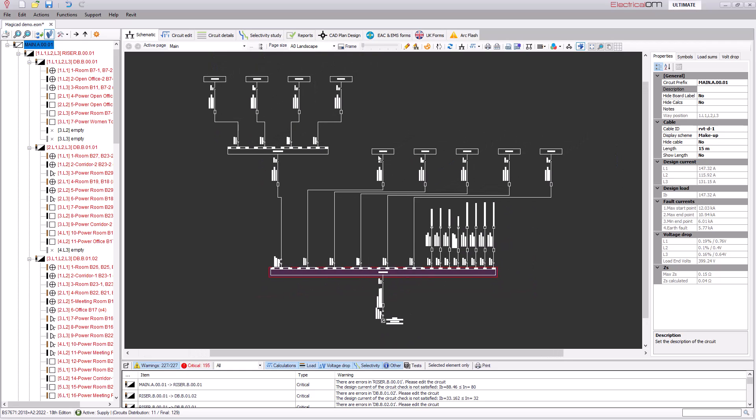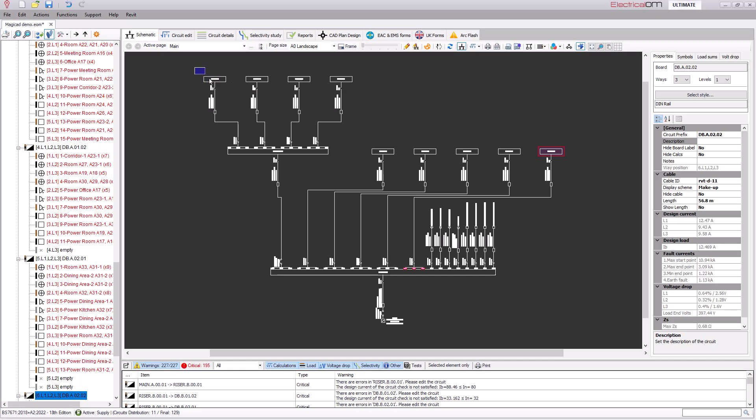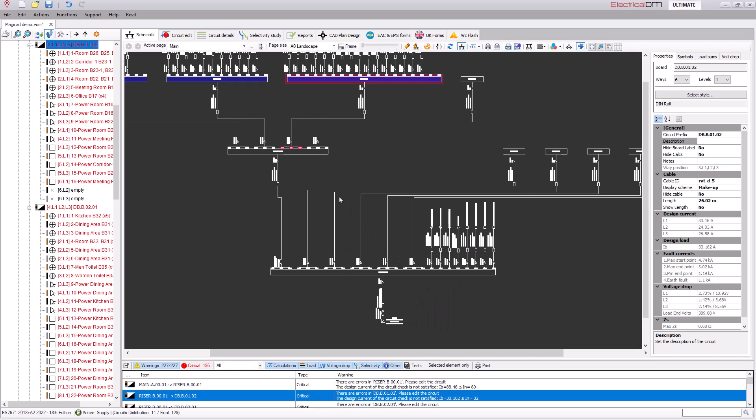Then all the elements downstream for this we can use the auto refresh option. Although the final circuits are not physical within the schematic, you'll notice within the tree network all of the final circuits are included from the update from the MagiCAD model. The final circuits are not currently visible in the schematic because the system is set to be in compact mode. This means that the distribution circuits will show but our final circuits will be hidden. By selecting either an individual board or multiple boards by dragging over them we can leave the compact mode by going to the schematic functions and selecting the option to leave compact mode.